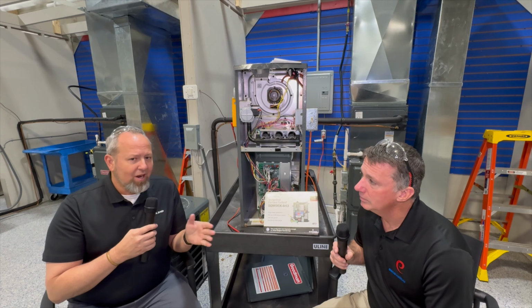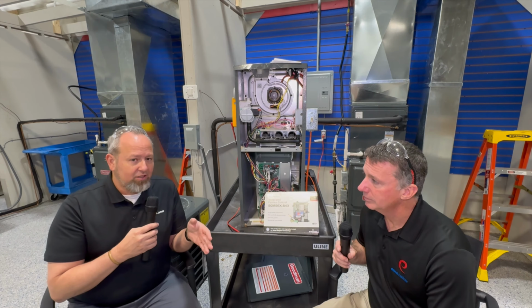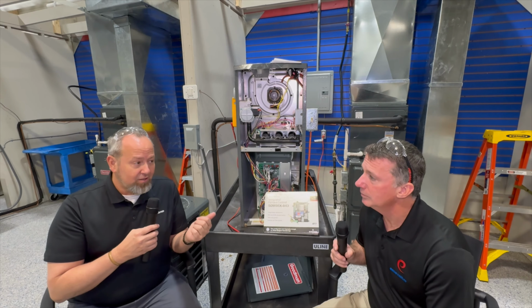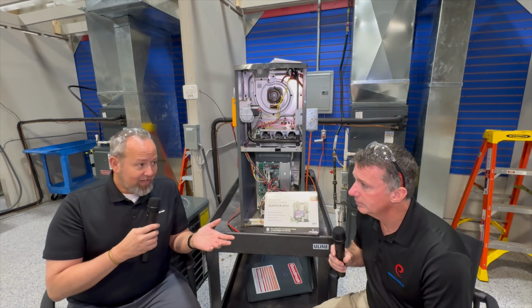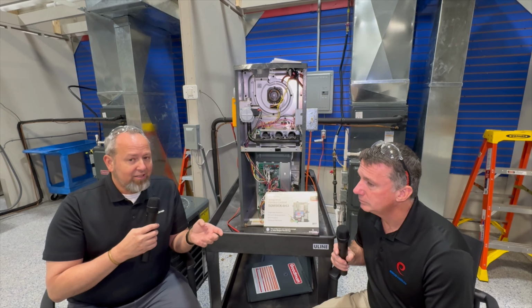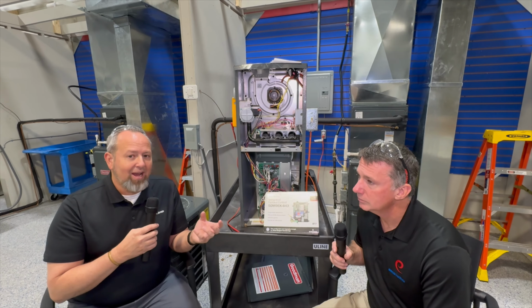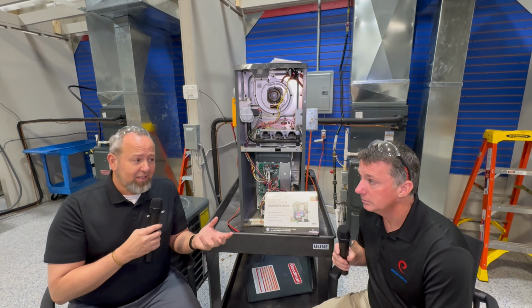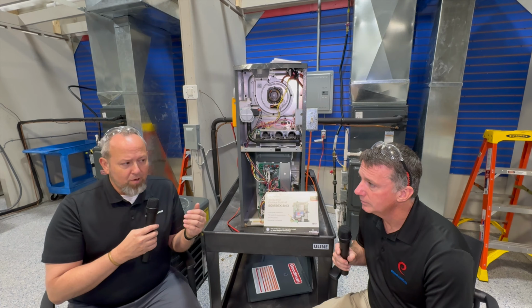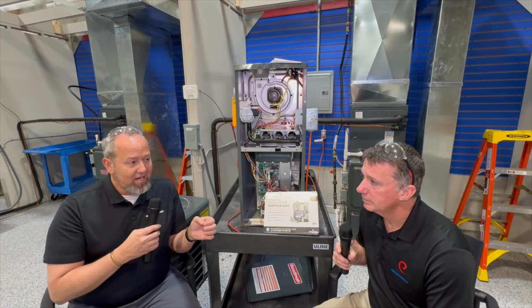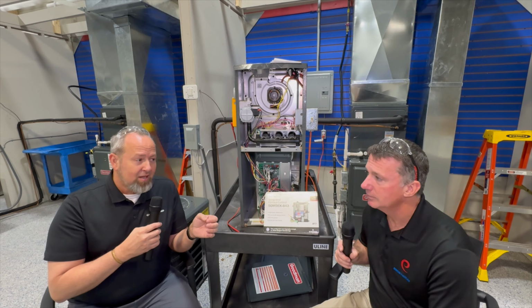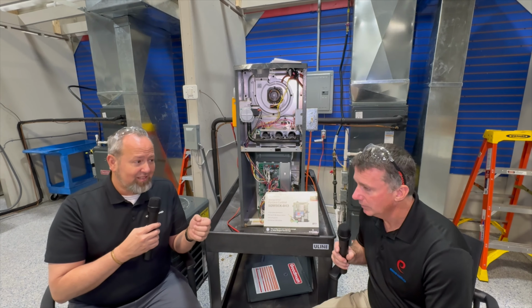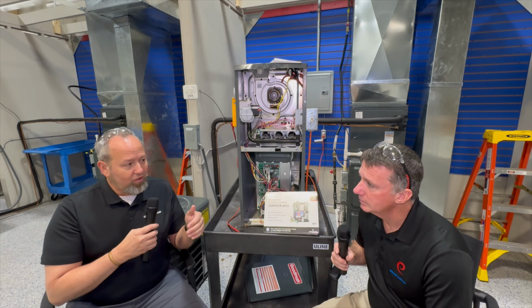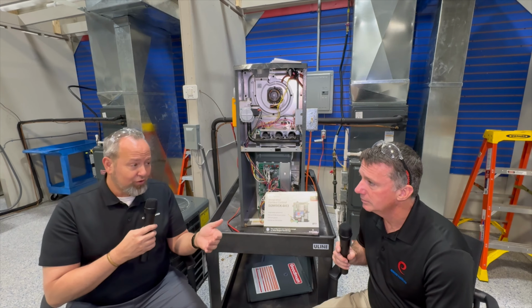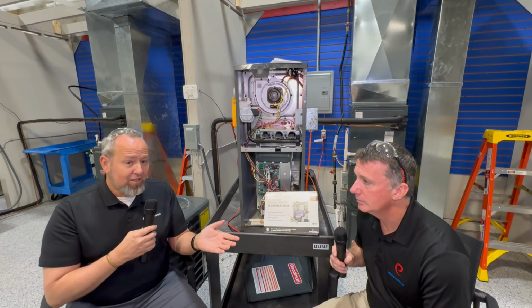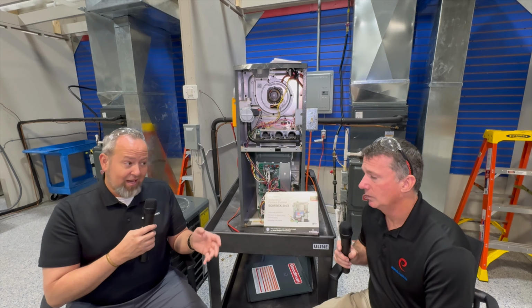Well, somewhere around the time that we actually saw the transition to ECMx motors in new manufacturing, the July 2019 mandate, motor manufacturers were also looking at the signal that their motor would take. From that point forward, most across the board, these motors will take a DC signal, and that DC signal can be anywhere from 9-volt DC all the way up to 18-volt DC. And that DC signal will work even on old control boards that would have sent a 24-volt AC signal to the motor — the motor will still receive that DC signal and turn on that way.